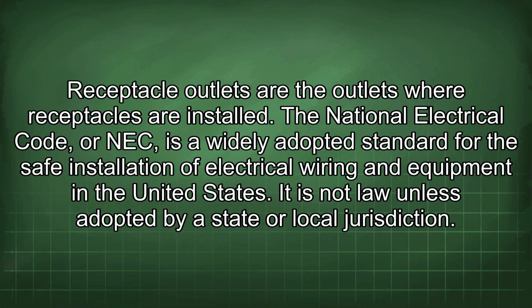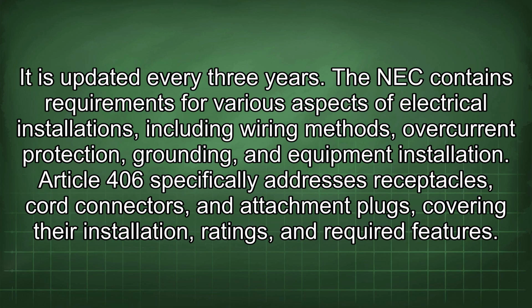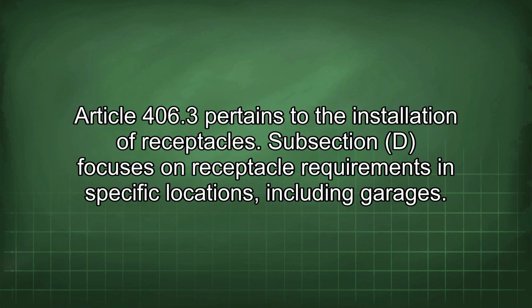The National Electrical Code, or NEC, is a widely adopted standard for the safe installation of electrical wiring and equipment in the United States. It is not law unless adopted by a state or local jurisdiction. It is updated every 3 years. The NEC contains requirements for various aspects of electrical installations, including wiring methods, overcurrent protection, grounding, and equipment installation. Article 406 specifically addresses receptacles, cord connectors, and attachment plugs, covering their installation, ratings, and required features. Article 406.3 pertains to the installation of receptacles. Subsection D focuses on receptacle requirements in specific locations, including garages.